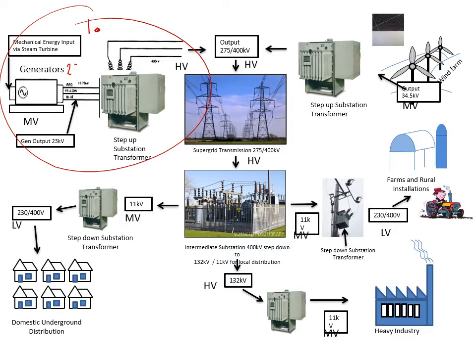The generator produces a high voltage — around 15 to 25 kilovolts. The reason we generate at very high voltage is because at high power levels it keeps the current down, meaning the current flowing in the windings of the alternator is significantly smaller, so the losses are effectively a lot less and it runs a lot cooler. Once we've generated 25 kilovolts, we go into a step-up transformer.